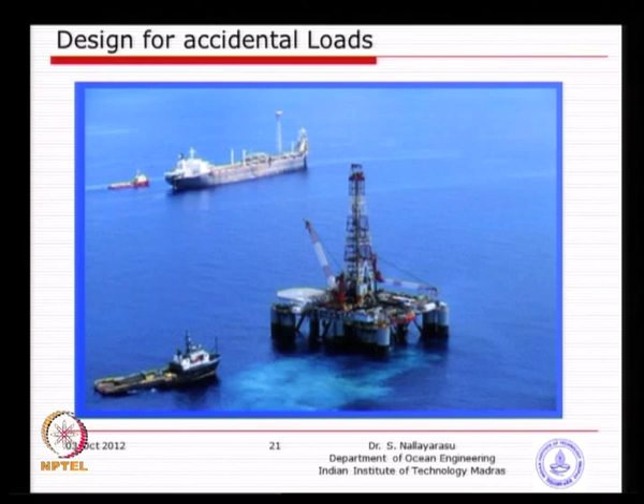So, what we need to look at basically is design against fire. You need to find out what type of fire it is, whether it is a pool fire or a jet fire, which I think we will just quickly look at. Pool fire: basically, if there is a spillage on the floor of a particular location, a large amount of fuel, then the fire will be almost like a spread fire, just over a larger area. So, you have the fuel spillage on the ground or on the floor somewhere, whereas in a jet fire, there is a high pressure fluid, hydrocarbon oozing out of a pipe, a bigger tank or a process equipment. So, basically it will come like a high speed jet, which can go for a longer distance, number one, and destroy several things which are secondary in nature, for example cables and facilities.